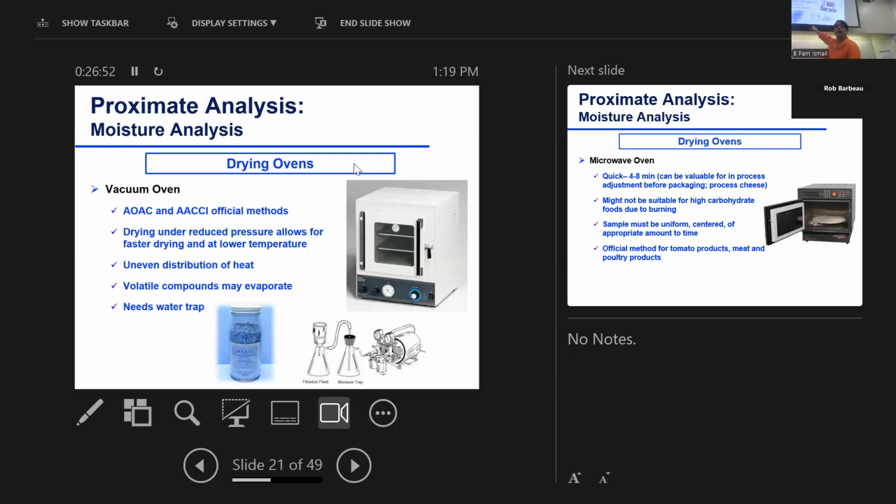Did you see that in the lab? Yeah. And was there a desiccant in it? Yeah. So the desiccant in it collects that moisture in the form of vapor, and when it comes to room temperature and regular pressure, it condenses and gets collected before it gets to the pump. So you're trapping moisture before it gets to the pump.